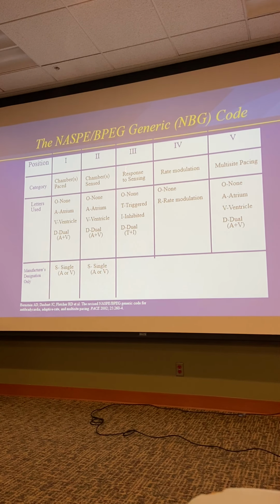When someone has an ICD instead of a pacemaker, and you apply the magnet, it doesn't do anything that we just talked about. The only thing a magnet does on an ICD is turn off the ability to shock for VT or VF. So if someone's having inappropriate shocks, that sort of thing, you'll see us put a magnet on or even tape a magnet in place, and it's not having any effect on the programmed pacing characteristics the way it would for a pacemaker.